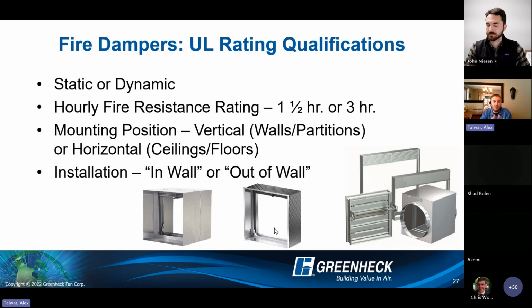Typical installations are standard, in wall. The damper will have no problem being within the wall. It's only those specialized installations, maybe shaft wall, where you want that internal grill access, where you might need that out of wall access, or out of wall damper, sorry. But again, it is important to know up front: we can't just convert these dampers in the field. They're built a certain way to a UL spec, based on when we test and qualify these products.